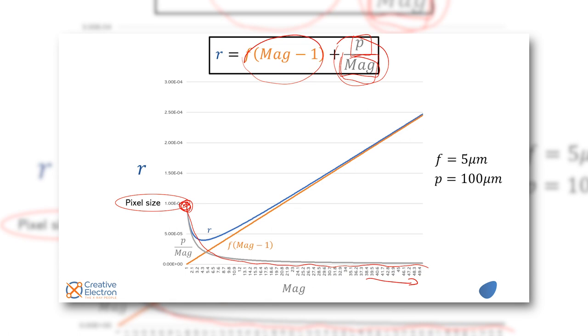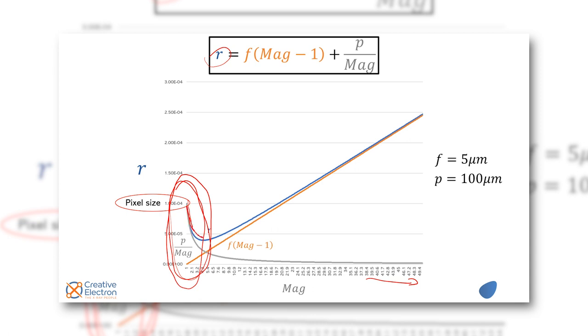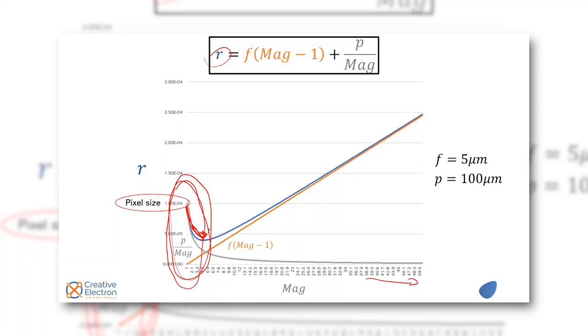Now when you put it all together, that's our blue line here. What we see is that for small magnification the detector drives the resolution. As we increase magnification our resolution gets better and better and better because we follow this gray curve here, gets better until the focal spot takes over.